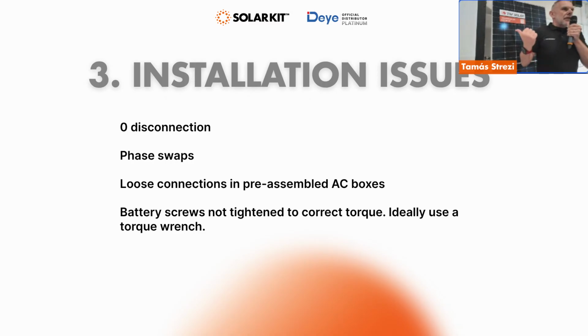There is a really funny picture in the booklet of the inverter when you're supposed to tighten it with a flathead screwdriver. That's totally unacceptable. You need a proper wrench and a 17 millimeter socket and tighten those connections properly. You would be surprised how many electricians did not do this. And over the long term, it's a fire hazard. Just one important thing at the end, despite seeing these inverters running incorrectly set up for months, really consuming lots of energy and being really hot in many cases, I'm yet to see a definite failure of an inverter. So I think there is a good base.